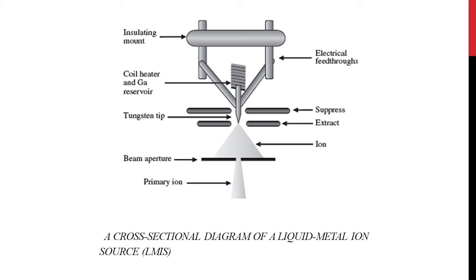We have two coils — a suppressor and extractor coil. When you heat up the gallium reservoir, all the gallium atoms flow through the tungsten tip and form a point source. The extractor coil helps pull the ions from the tungsten tip, and the suppressor coil suppresses the voltage to maintain an emission of 2.2 microampere. Once the ion beam is formed, it passes through a set of apertures which defines the beam diameter. Once the beam diameter is defined, the primary ions start scanning your sample and give you an image on the monitor.